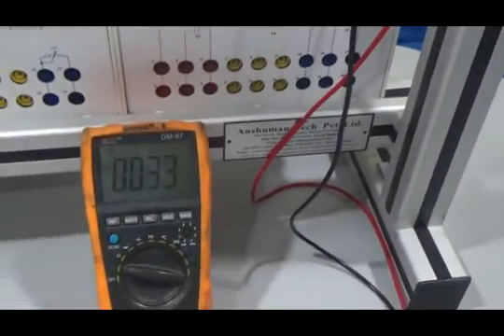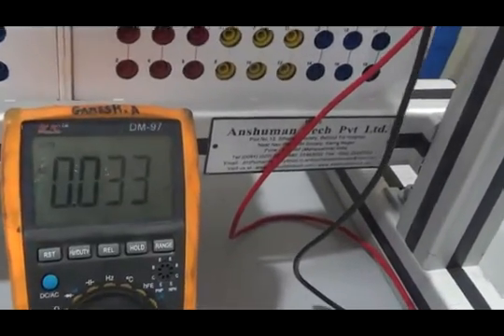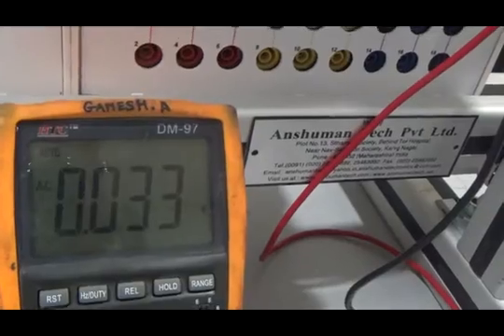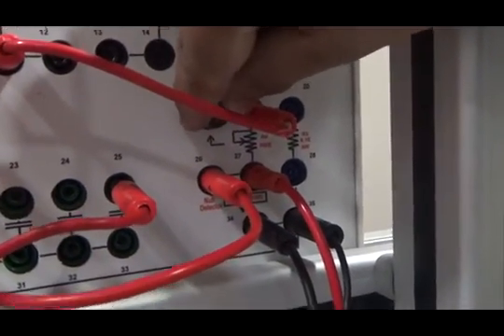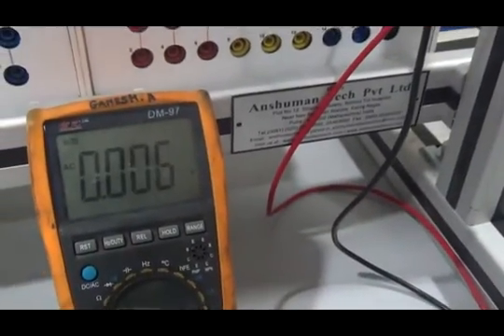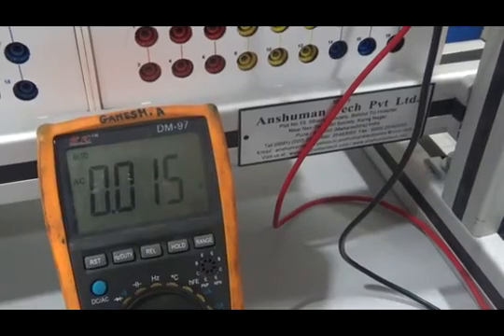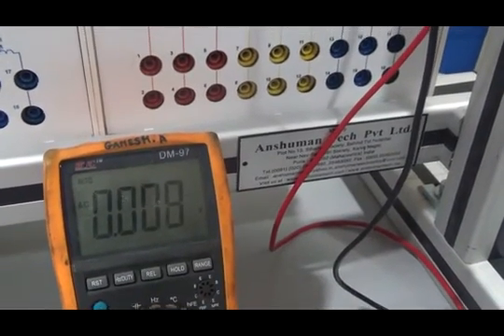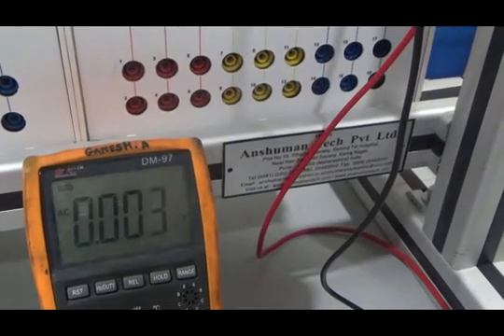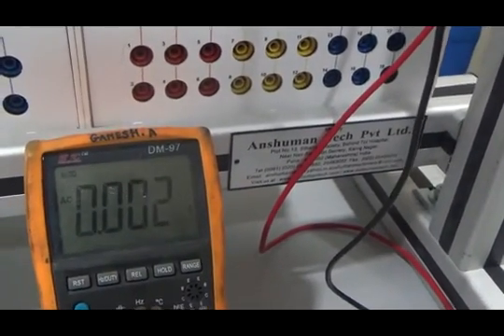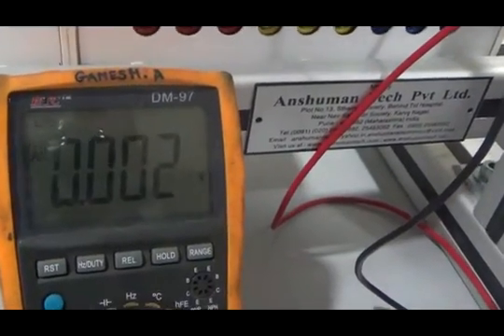Now observe on external digital multimeter if there is some error. This error can be removed by using balance phase error potentiometer provided on this panel. So rotate this potentiometer in such a way that you will observe a zero error on this meter. So keep adjusting the phase angle error potentiometer until you get zero volt error.